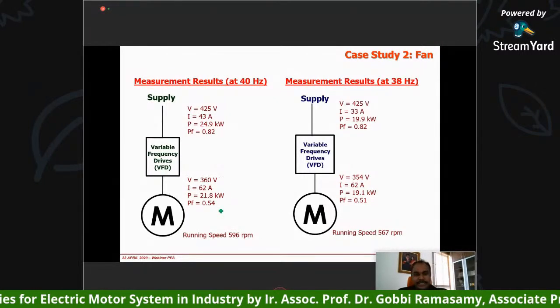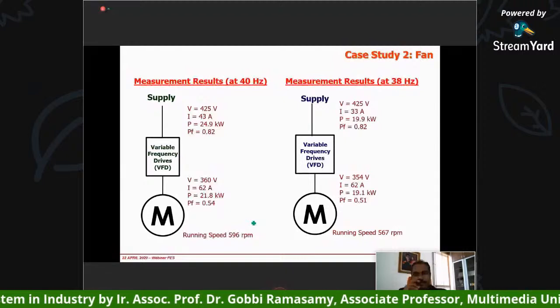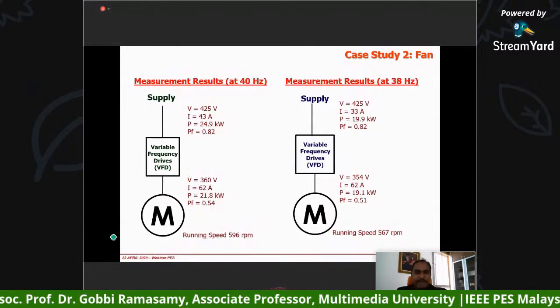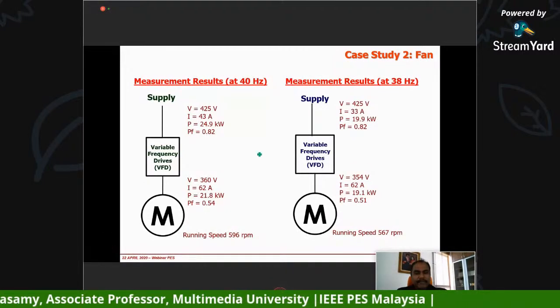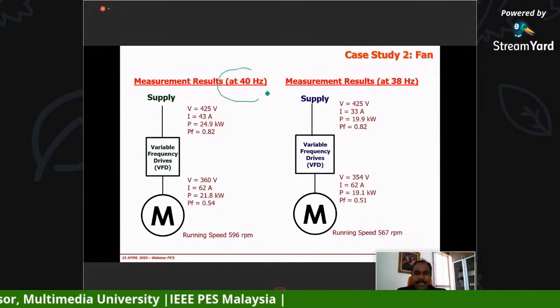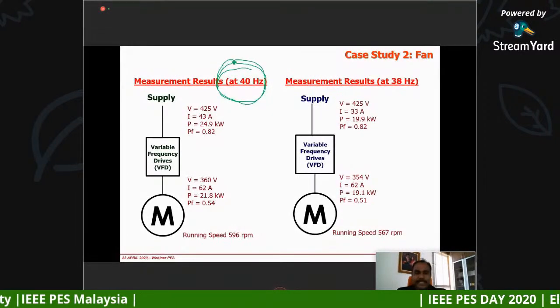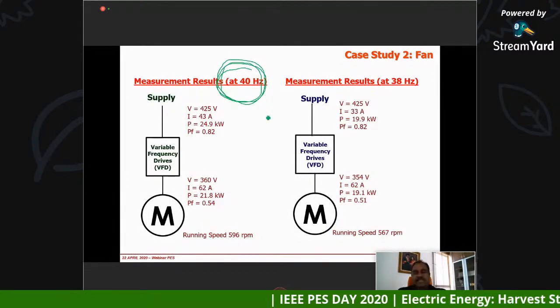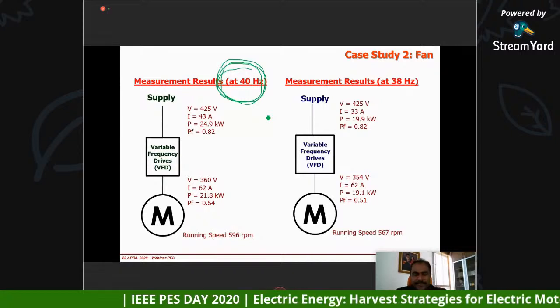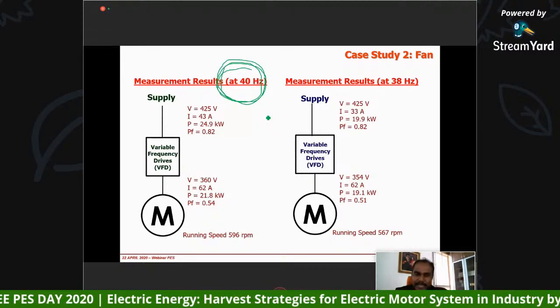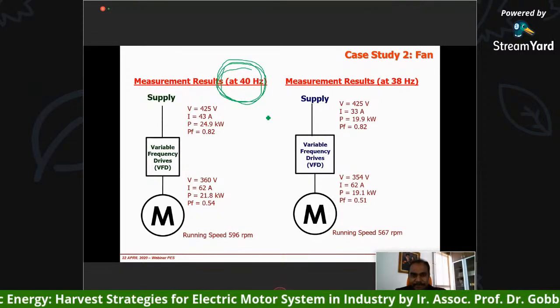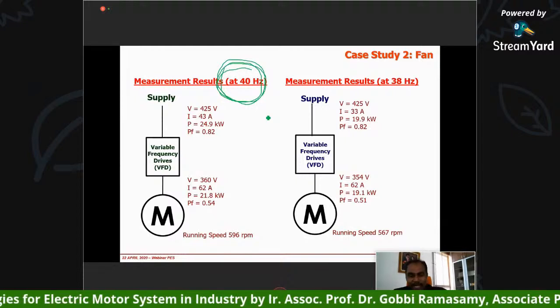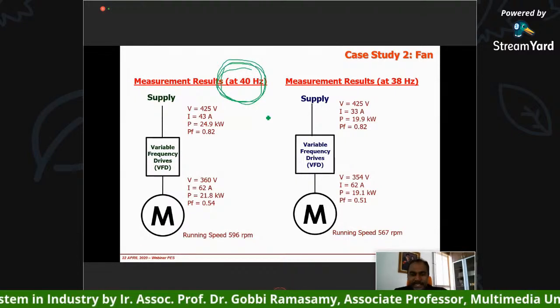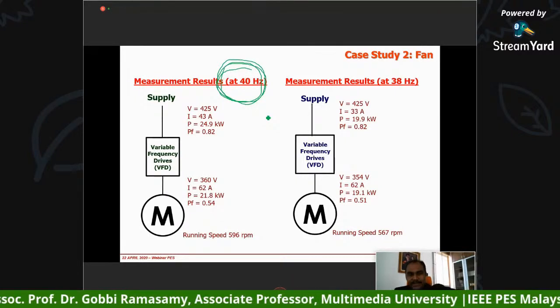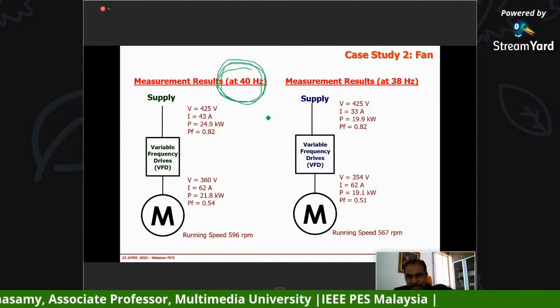Now, yes, this particular motor was already connected to a variable frequency drive, and all the while they were running at 40 hertz. This again happens in industry. They already installed the VFD, and then they probably preset a certain frequency. And when we go and ask the technicians and engineers, okay, why 40 hertz? They said it's already preset. You're not allowed to change it. But it's not true.